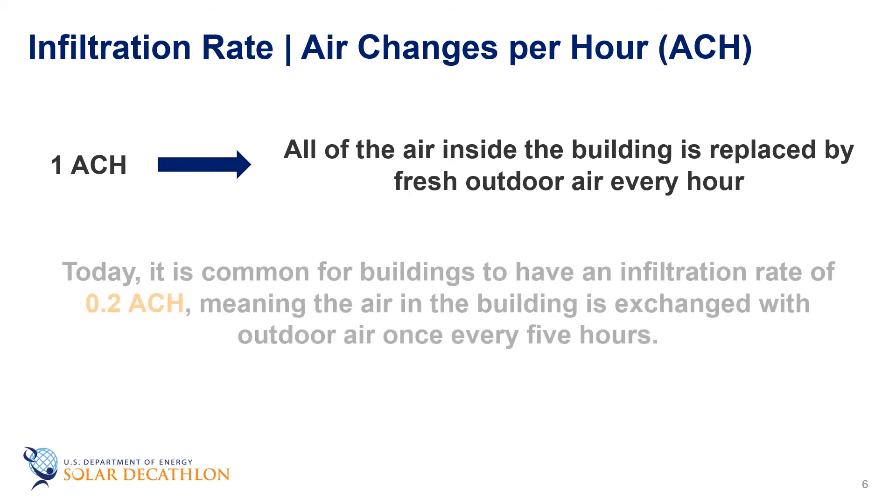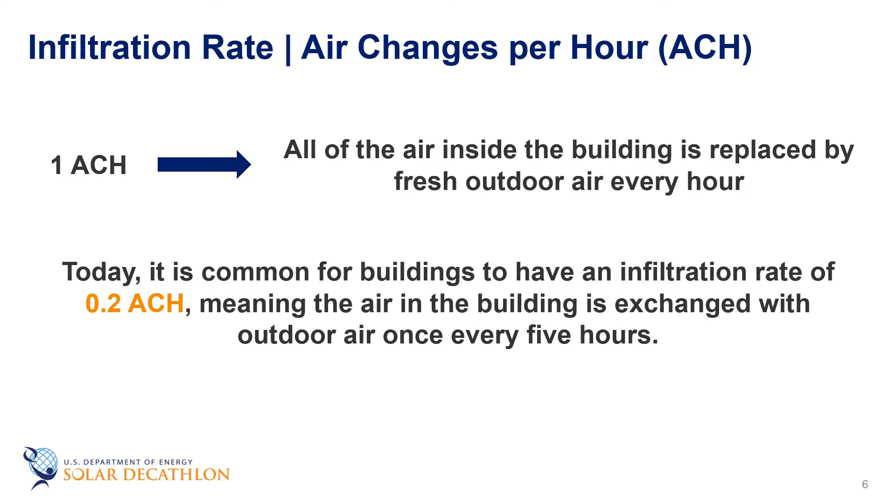For example, if we have one air change per hour, that means all of the air inside the building moves out of the building, and fresh air is added to the building every single hour. Today, that would be a fairly leaky building, but it wasn't that long ago where this was typical. Today, we often see buildings that are less than 0.2 air changes per hour, but even with that, that would mean that every five hours the air is completely exchanged from indoors to outdoors.